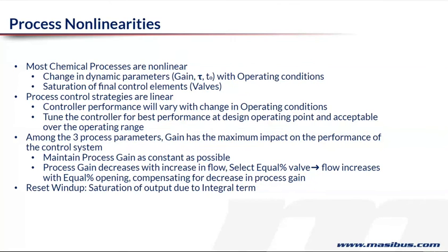So you have to be aware of that, right? It's not like one equation or one PID tuning will fit for all set points. So you have to be knowledgeable about the process, whether it is linear or non-linear. If it is non-linear, then every time you change your set point, you have to also retune the PID controller.